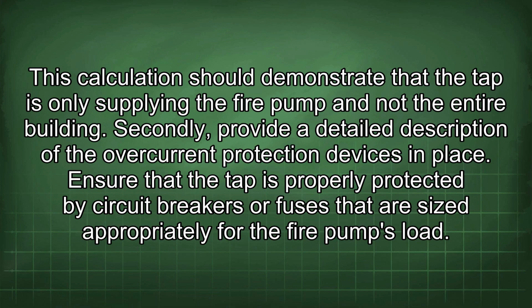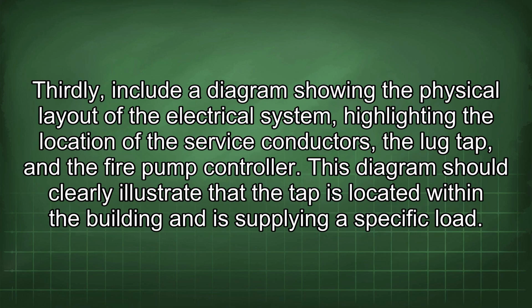Secondly, provide a detailed description of the overcurrent protection devices in place. Ensure that the tap is properly protected by circuit breakers or fuses that are sized appropriately for the fire pump's load. Thirdly, include a diagram showing the physical layout of the electrical system, highlighting the location of the service conductors, the lug tap, and the fire pump controller. This diagram should clearly illustrate that the tap is located within the building and is supplying a specific load.